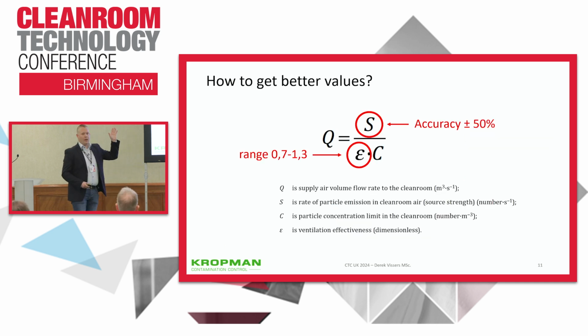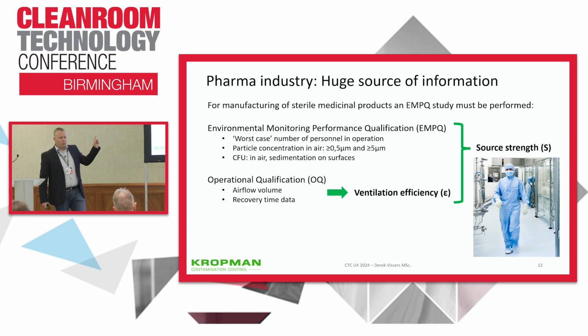So the question remains, in my opinion, how do we get better values for the source strength and the ventilation effectiveness? We, as designers, can be very happy or lucky with the pharmaceutical industry because there is already a lot of data available. Especially when we talk about manufacturing of sterile medicinal products, an EMPQ study must be performed to determine the critical EM locations in your clean room. During this EMPQ, there is maximum occupation in your clean room, so the maximum number of operators is in the clean room doing the process. So it's the worst case scenario.